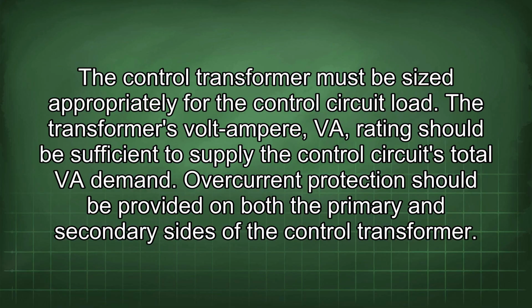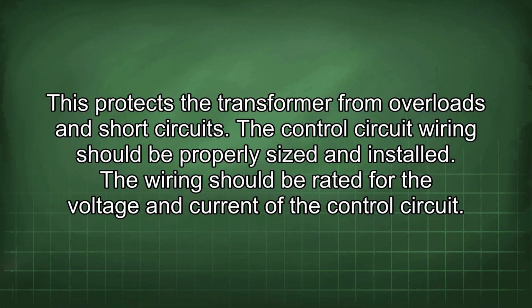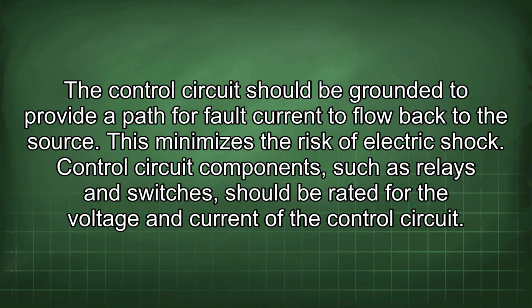Overcurrent protection should be provided on both the primary and secondary sides of the control transformer. This protects the transformer from overloads and short circuits. The control circuit wiring should be properly sized and installed. The wiring should be rated for the voltage and current of the control circuit. The control circuit should be grounded to provide a path for fault current to flow back to the source. This minimizes the risk of electric shock.